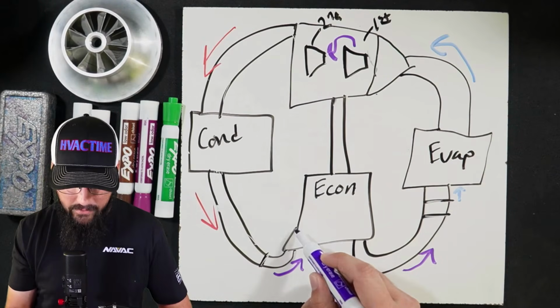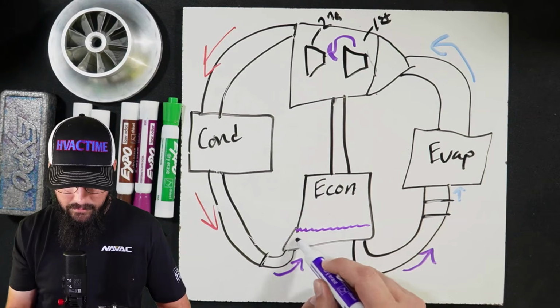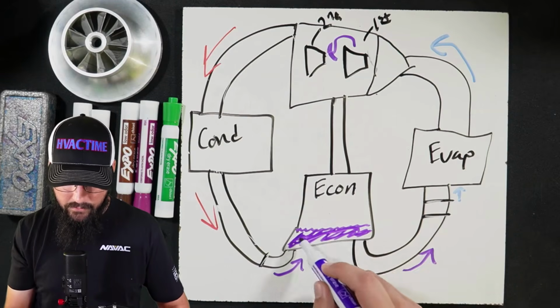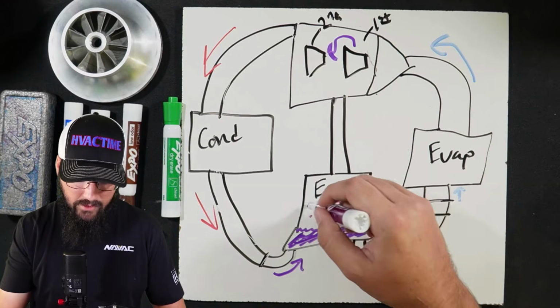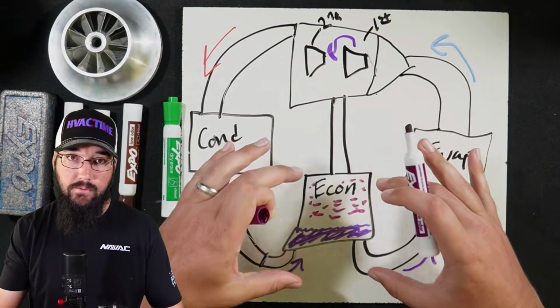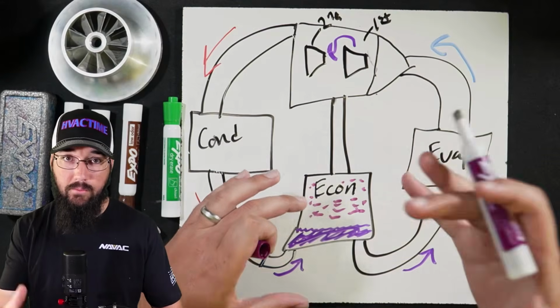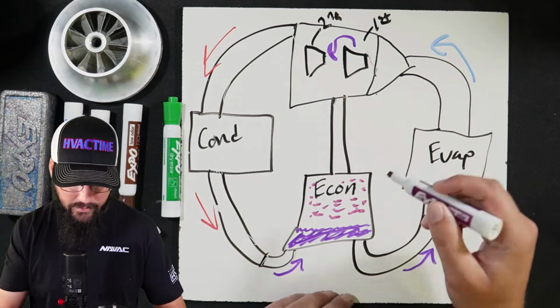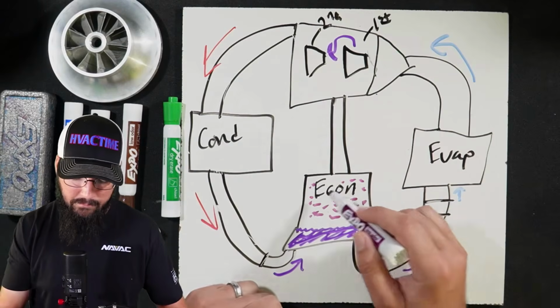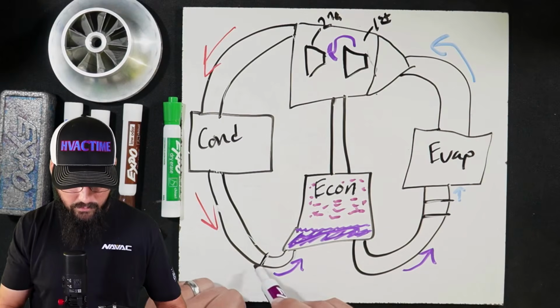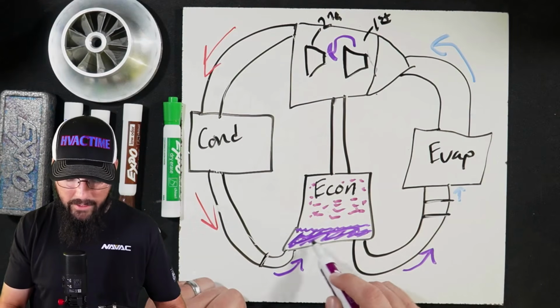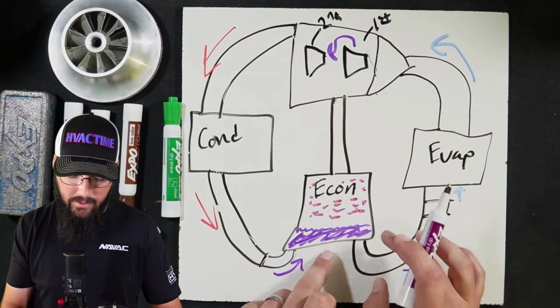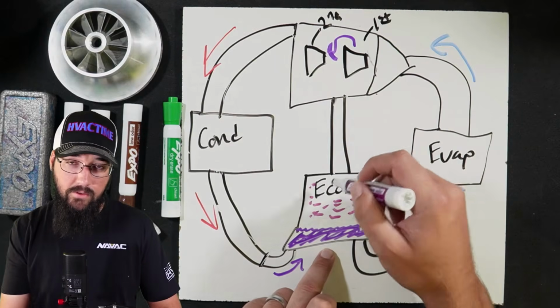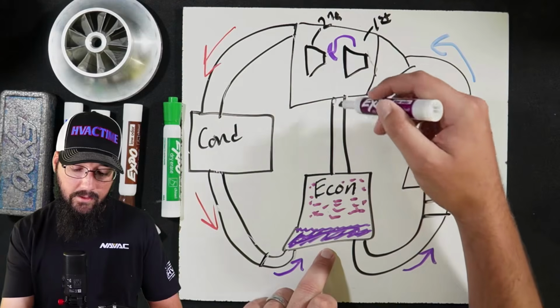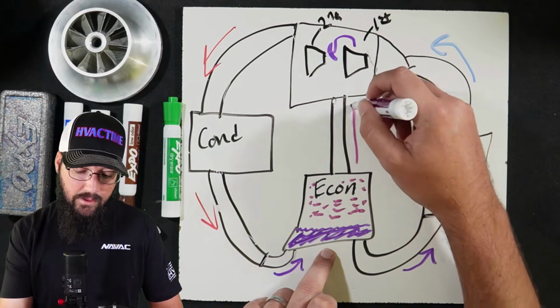So what we do, that liquid refrigerant doesn't change in subcooling value. This is all liquid in here. Liquid refrigerant will stay in the bottom, but our vapor, the flash gas itself, will rise to the top of this chamber. This is a big cylinder on the side of the chiller, right, with the economizer. So you're very, very specific to calling out the economizer in that process. That is what this is right here. Usually it'll be fully insulated. So we have our first stage of pressure drop. We have our 80% liquid that stays here in a medium pressure state. That medium pressure vapor rises to the top of this chamber, and there is a pipe on the top of that then feeds up into the compressor.